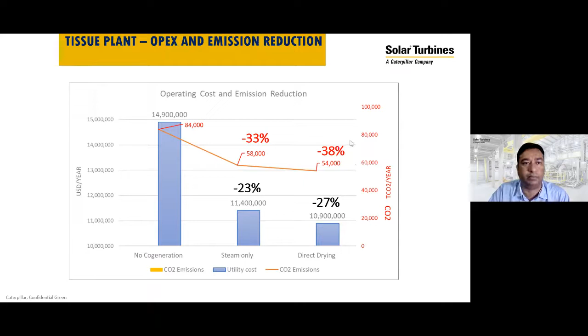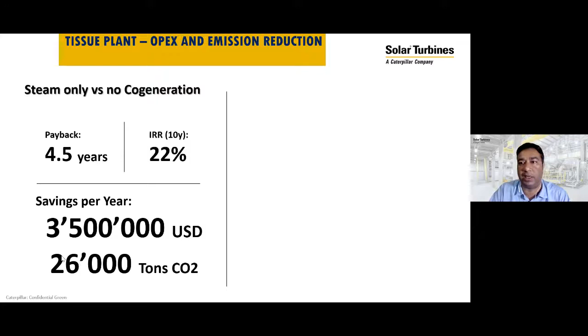So GT plus HRSG steam-only solution, compared to no cogeneration plant, will have in this case around 4.5 years of payback. The annual money saved will be around $3.5 million US, and CO2 emission will be reduced by 26,000 tons.